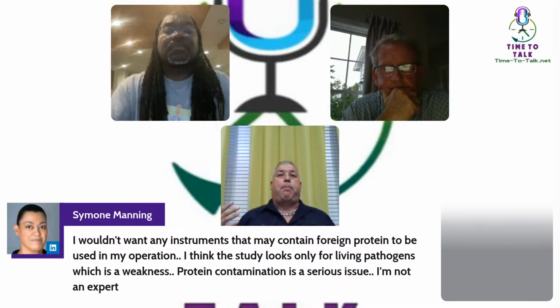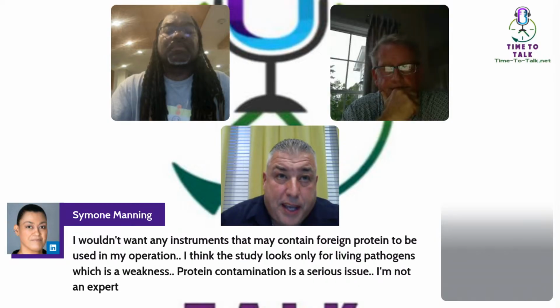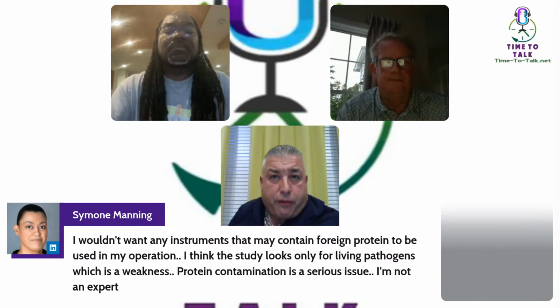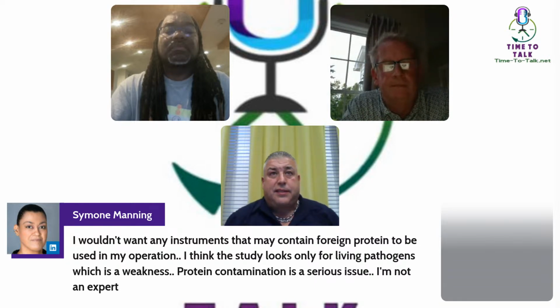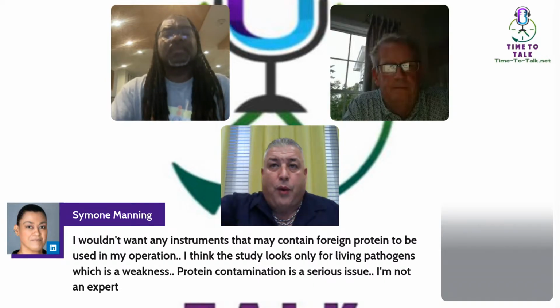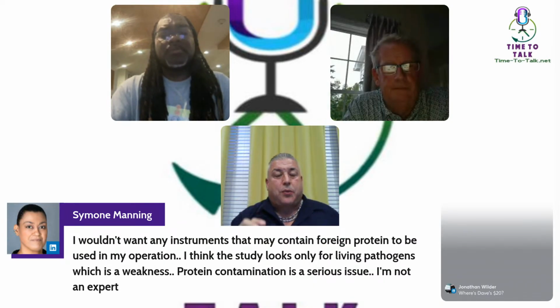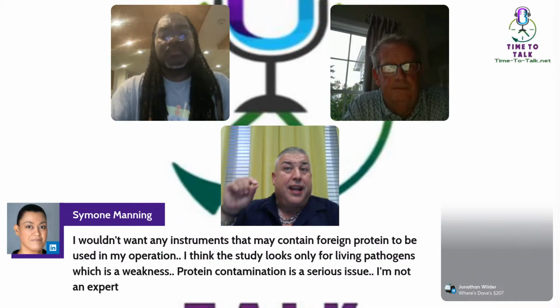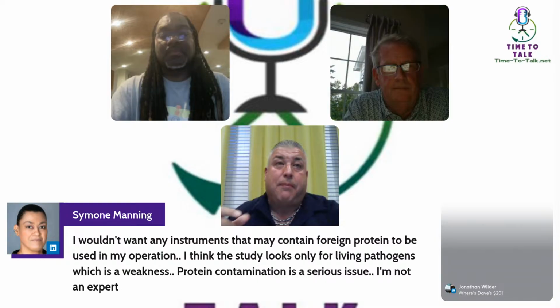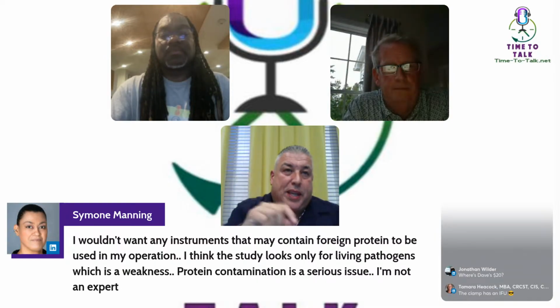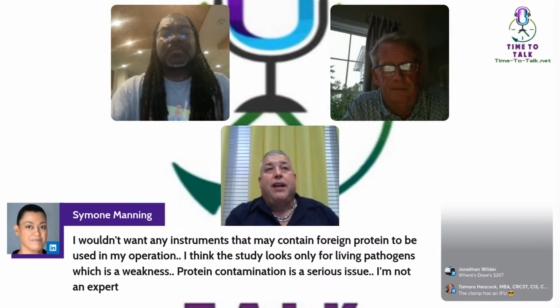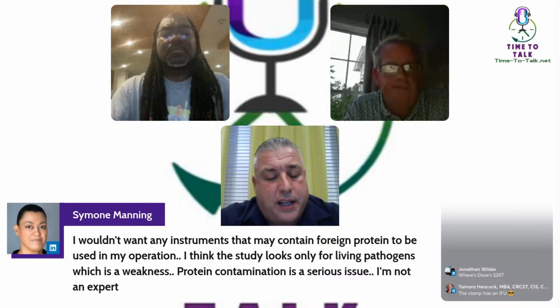When the device shows up in our department, we're not equipped. Certain hospitals in Europe, they're under pharmacy. They're run by PhDs. They do parametric release. It's a different world. But in the States, we receive those items, and to the best of our ability, we try to verify what the validation did. We try to mimic it as best we can. Look at the way this particular study was done. They inoculated. They took organisms and placed them. We have self-contained biological tests. We can't crack those open and pour them down lumens to do sort of our own studies. You can do those types of studies, but they're not typically done in the U.S. That I've seen.